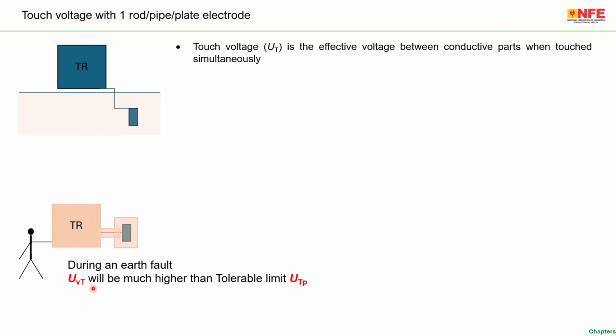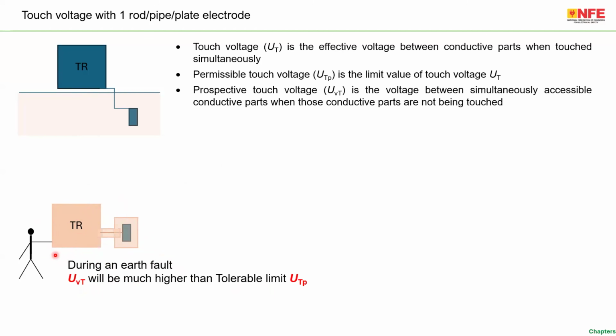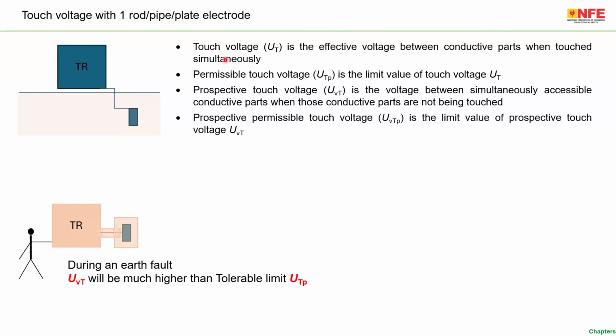During an earth fault, UVT, the prospective touch voltage, will be much higher than the tolerable limit. The actual touch potential created in this area, for example, if 3 kV is the UE, then the touch voltage may be about 1500, 1600 volt. A person who is standing there and touching it is literally dead, because the touch voltages are much higher than the tolerable limit.